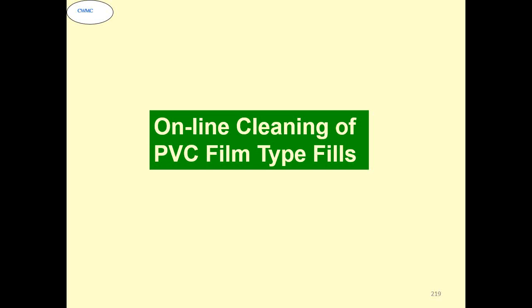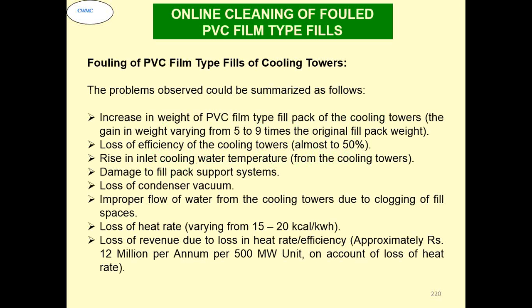Now the last item of this series is the experimental work that we had done, the development of online cleaning of PVC film type fills of the cooling tower. Normally, PVC film type fills, once they are there, are prone to fouling, and because of that there is a gain in weight.